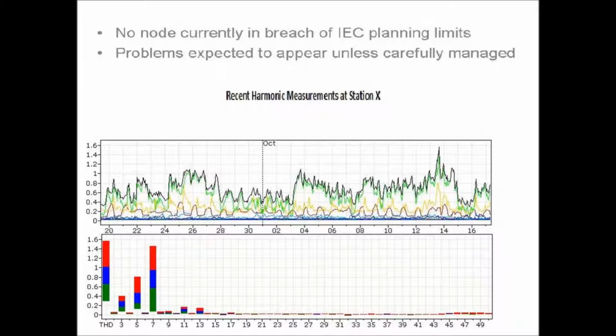You can see the green line just underneath the black line is the dominant harmonic. That's the seventh, and that's not a particularly good harmonic to have, because it can affect your generators and your motors and things like that. We know that it's caused by electronic converters based on the equations earlier on. So basically we're being dominated by the 7th. This happened recently, from the 20th of September through to the 16th of October, so it's almost live data.